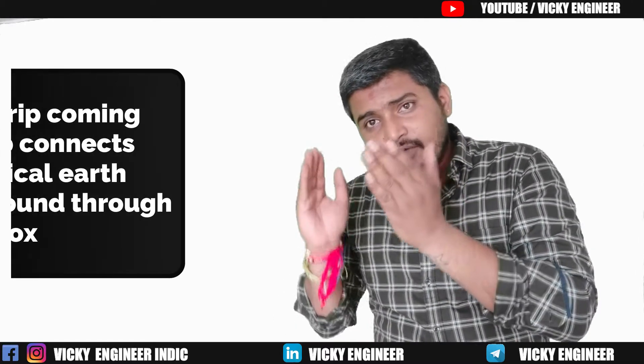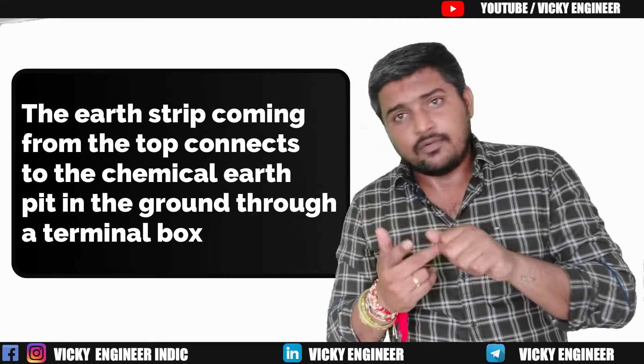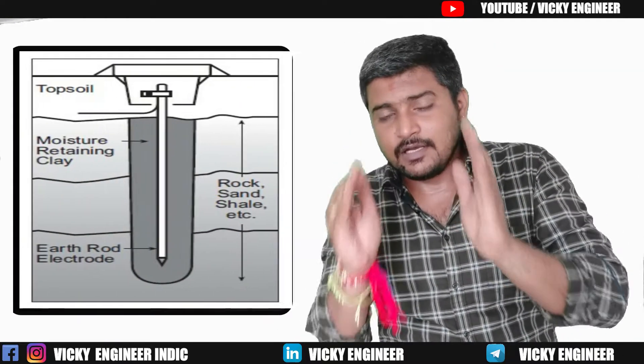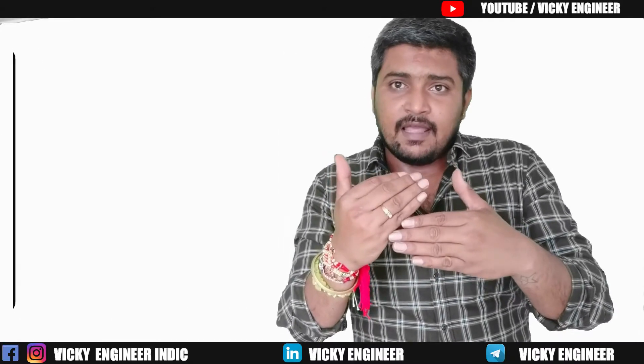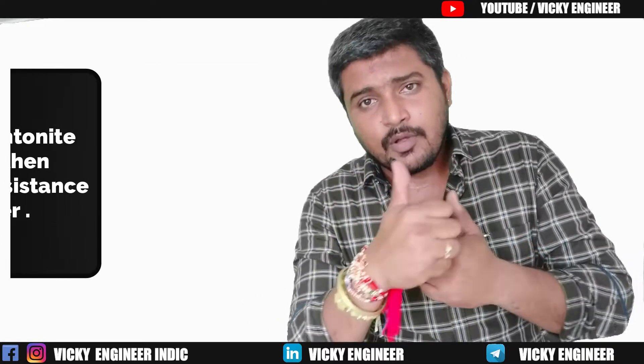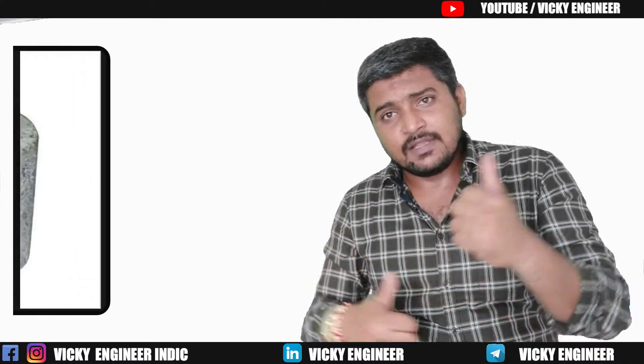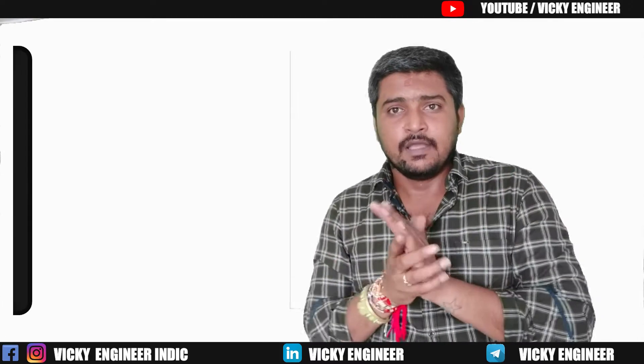Now, how is the lightning arrestor connected to the ground? There are two ways of grounding. First is conventional earthing, but for lightning arrestors, do not go for conventional earthing — always go for chemical earthing, because it provides stability for many years with low resistance and low resistivity. For example, Bentonite gives you around 3 ohm per meter resistance, and Marconite gives you 0.003 ohm per meter. If you don't know what chemical earthing is, I'm giving a link in the card button — go through that for good knowledge.